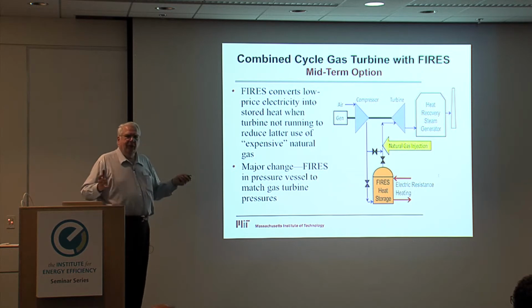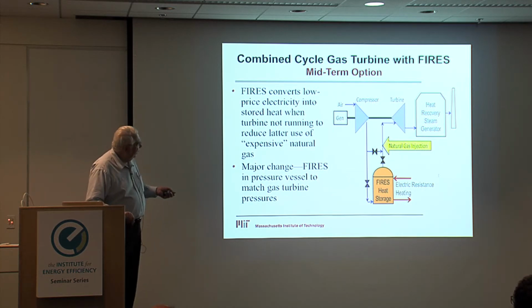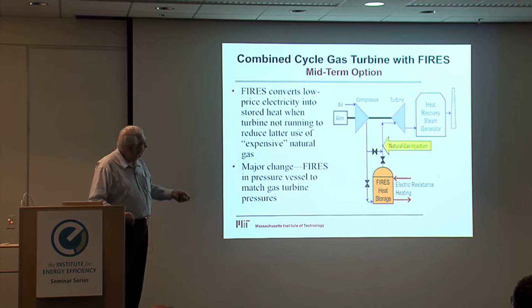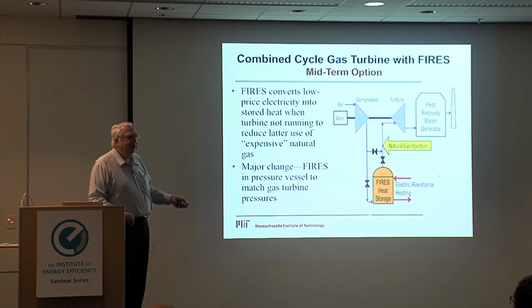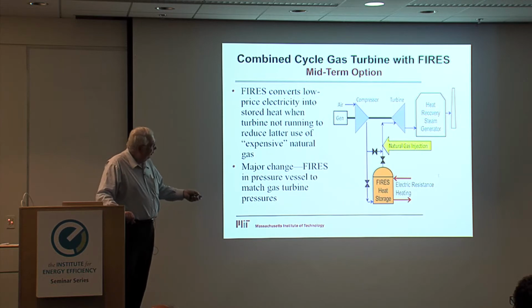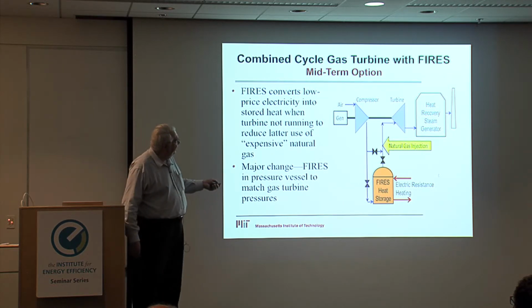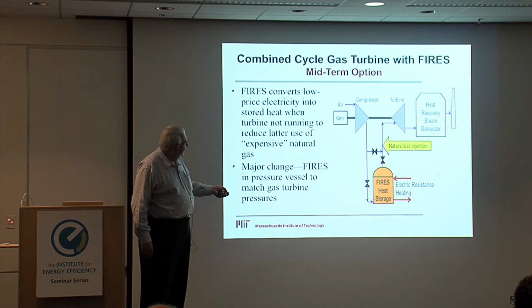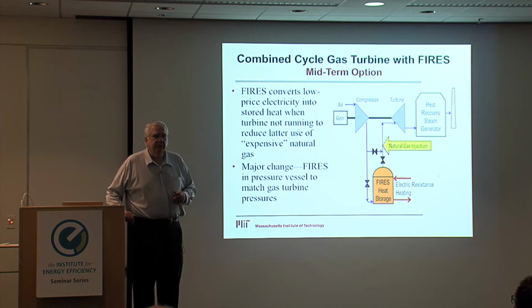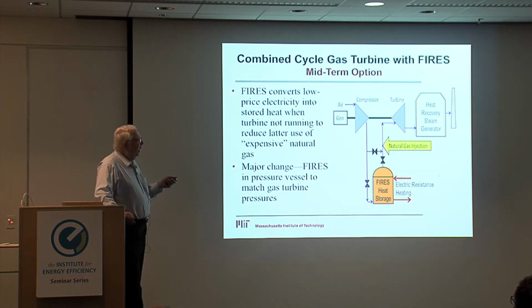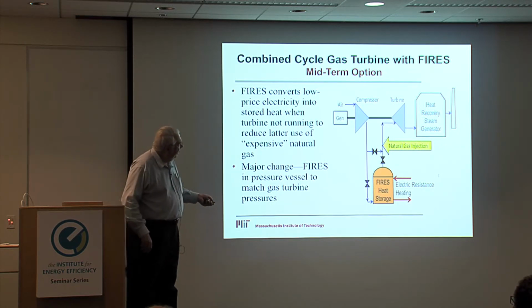However, California's got cheap electricity. So the next obvious idea is, when you have cheap electricity, what about heating up firebrick in a pressure vessel, to the same temperature as your gas turbine, say 1600C or 1400C or 1200C? When we have low electricity prices, we take our compressed air, run it through the firebrick, and replace some or all of the natural gas, then send it to the turbine and into the heat recovery system. In effect, it's high temperature heat storage in the firebrick.